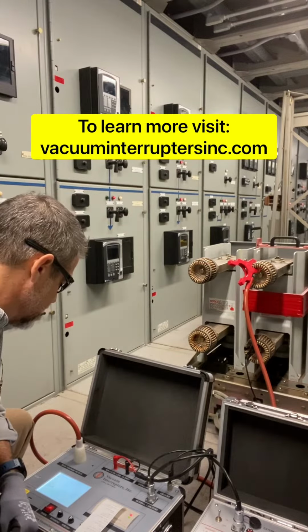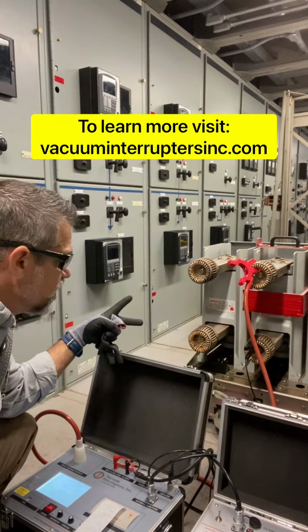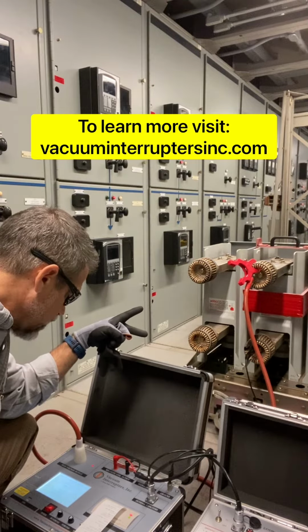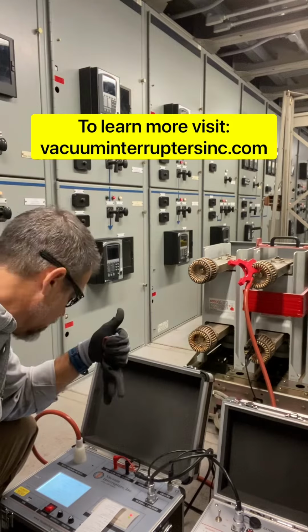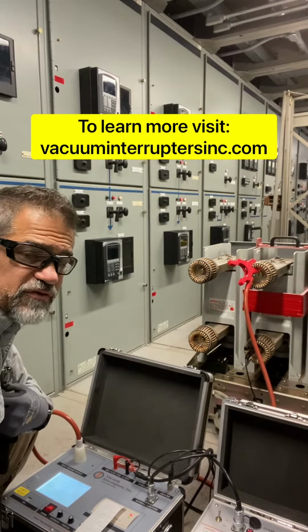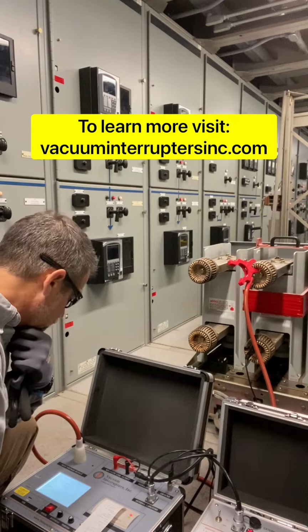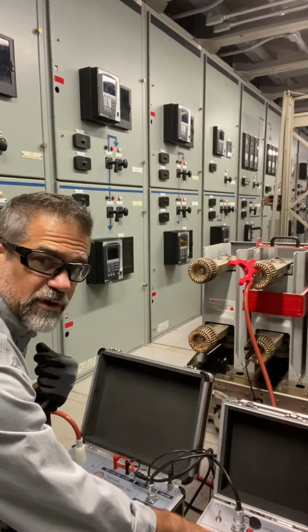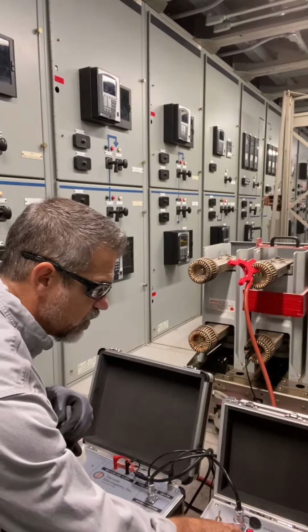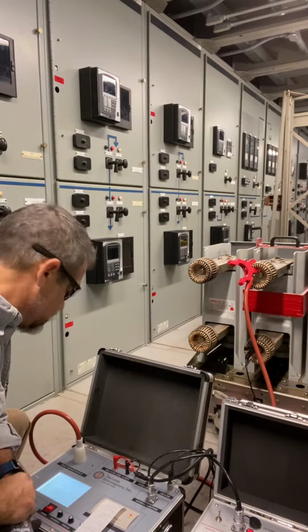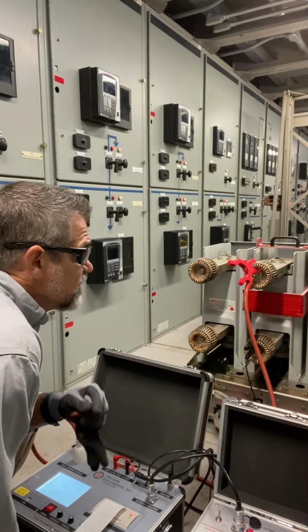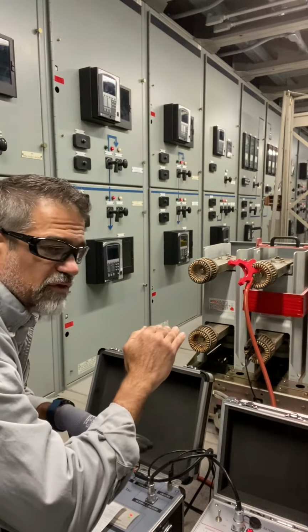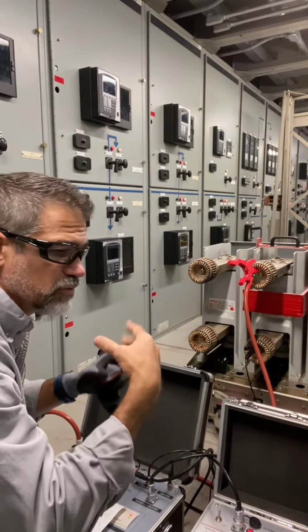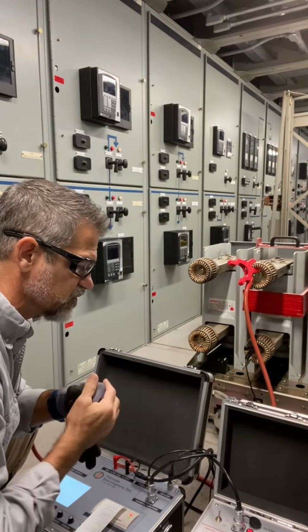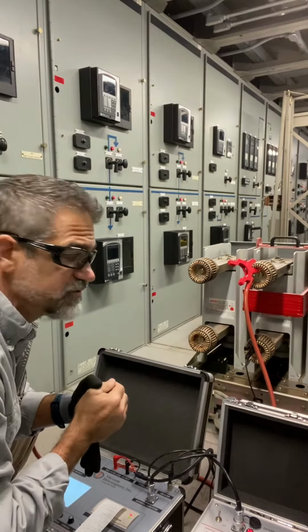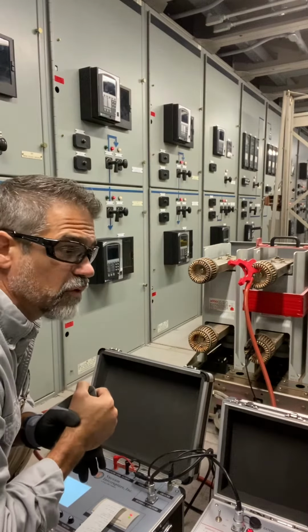You'll hear the test set beginning to do its thing. First it applies the 25 kV across the open pole and measures the leakage current to confirm we've got a good bottle, which we already know because we did an insulation resistance test on it prior to this. Now it's charging the capacitor. Unfortunately you can't really see the light here, but it's on, telling us the capacitor is charging. It's going to charge up to about 700 volts. When it gets to 700 volts, we're going to reapply the 25 kV DC across the pole, discharge that magnetic field from the capacitor's charge, and get a pressure reading. So stand by for that—we're at 350 volts.